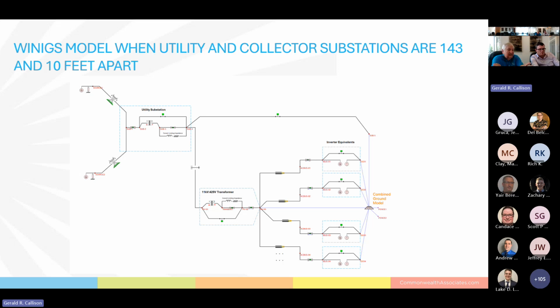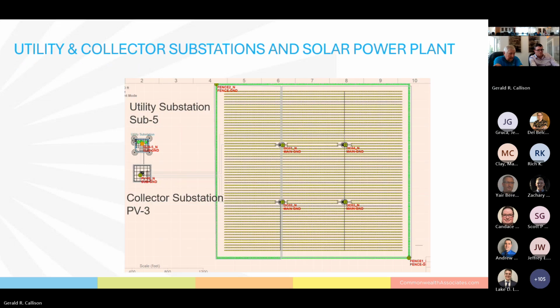So now we have to change the model slightly in WinIGS to put all 3 of the facilities in the model. Basically, it's the same model, except now we've got a ground connection between the utility, the collector, and the solar plant. They're all tied together. And the nomenclature had to change a little bit. So the utility substation is now sub 5. That's the ground grid there. PV3 is the new name for the collector grid. These stay the same in the solar plant.